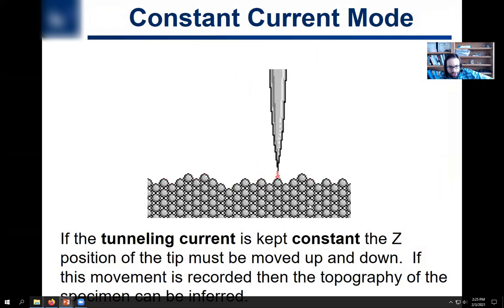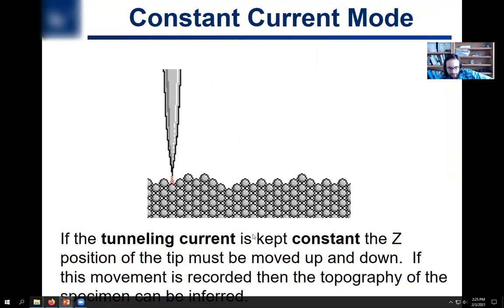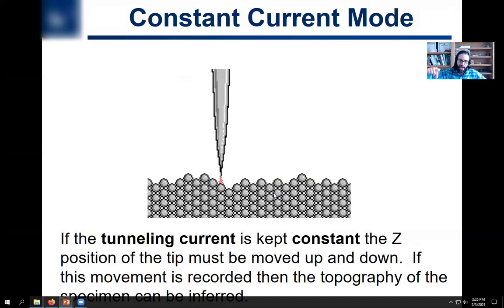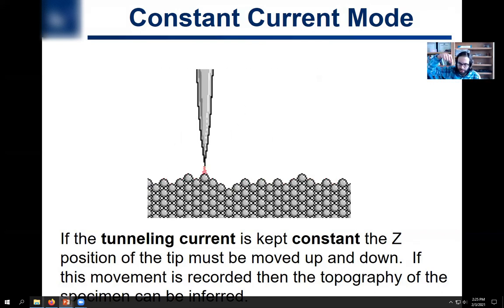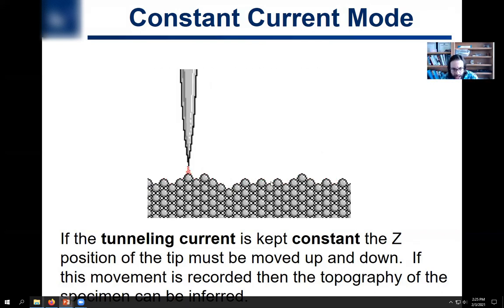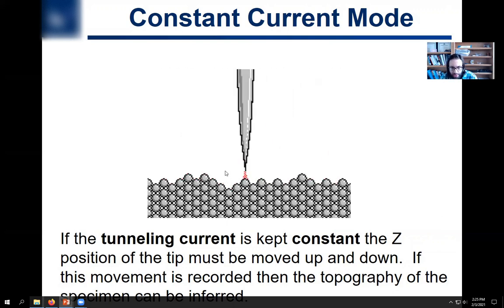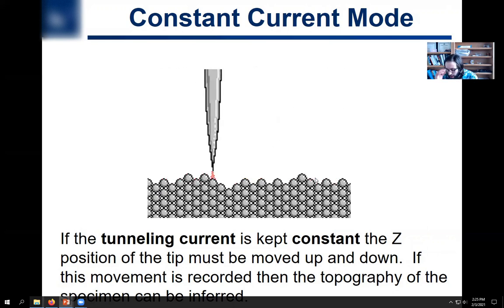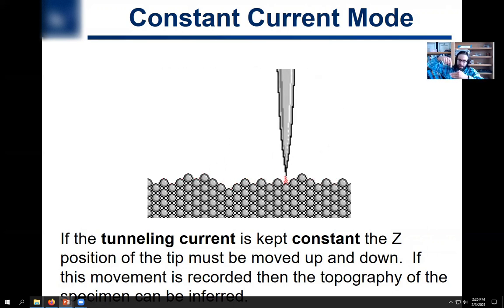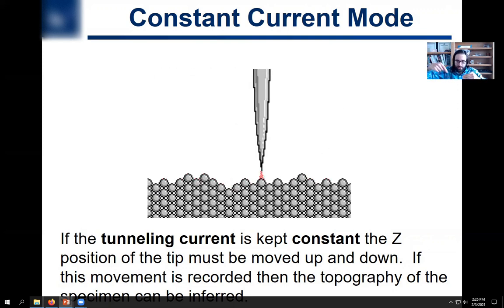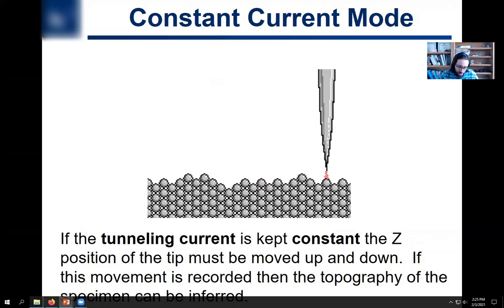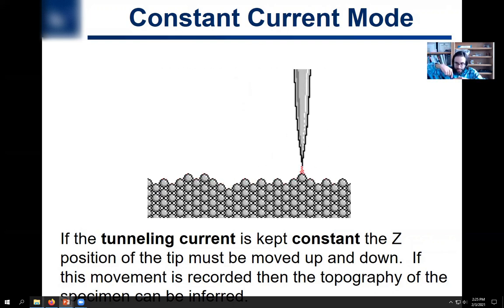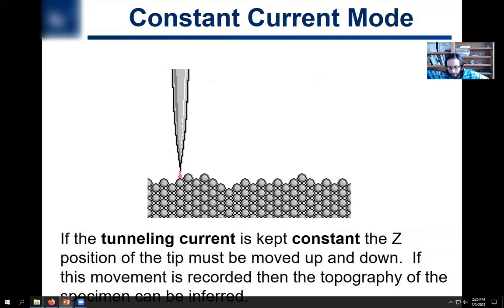There are two ways you can operate STM. One is keeping the tunneling current constant — this is called constant current mode. If you tell the instrument you want the tunneling current kept constant, as you raster across the surface, the tip is moved by the piezoelectric up and down so as to maintain a fixed distance where the tunneling current is fixed. By detecting how much the tip is going up and down, that's what gives you your topography.